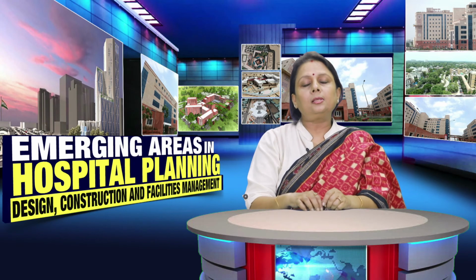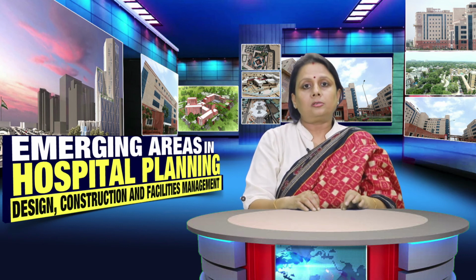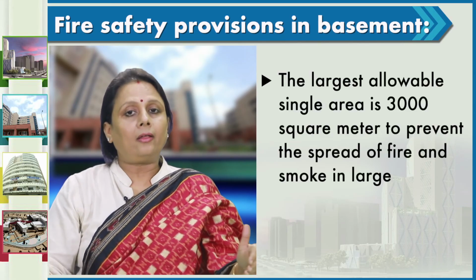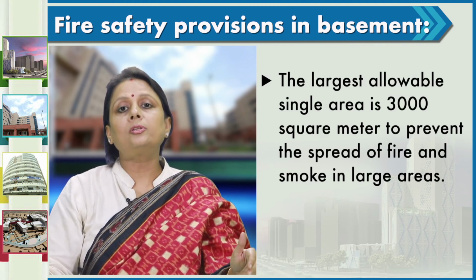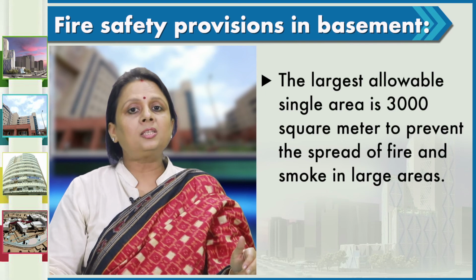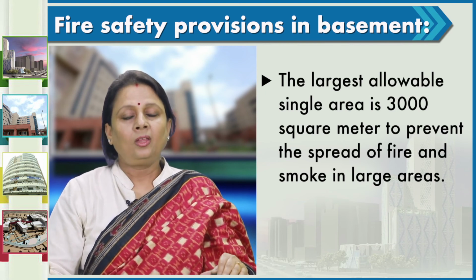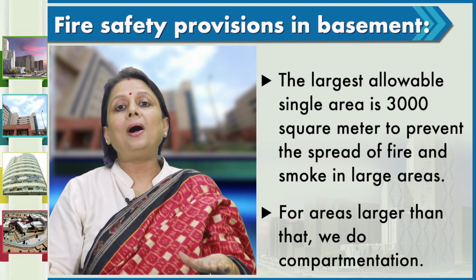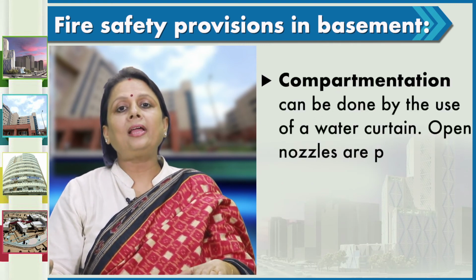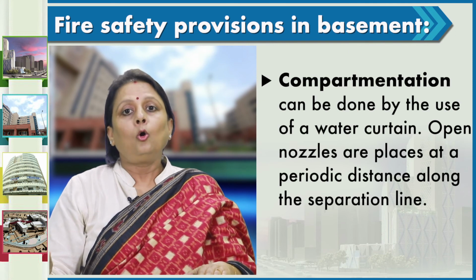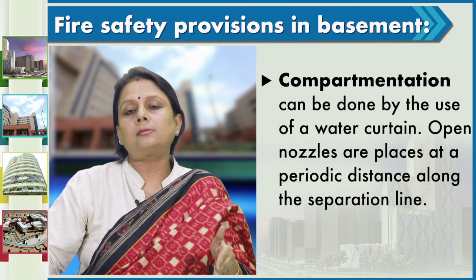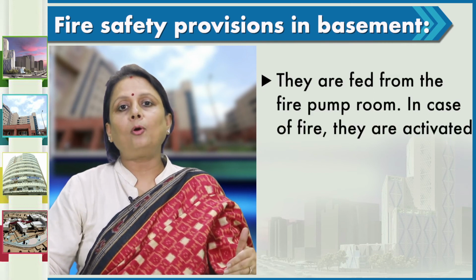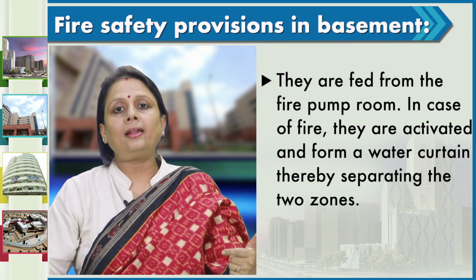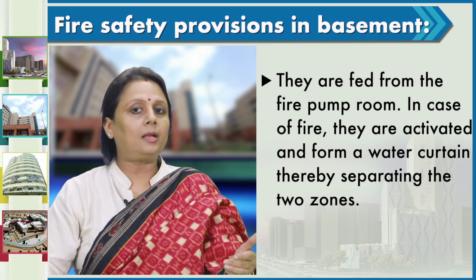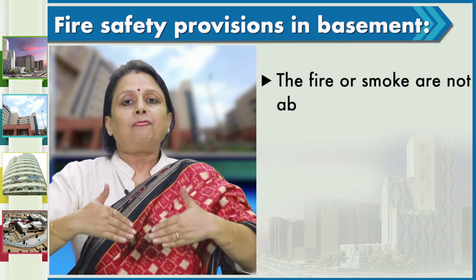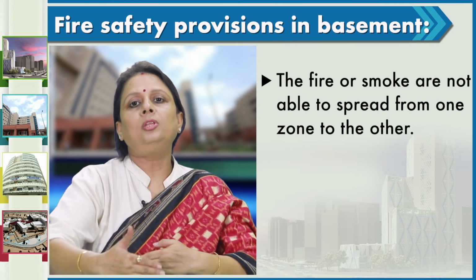Fire safety provisions in the basement are very important. The largest allowable single area anywhere, especially in the basement, is 3000 square meters, so as to prevent the spread of fire and smoke in large areas. For areas larger than that, we do compartmentation. Compartmentation can be done by the use of a water curtain. Open nozzles are placed at a periodic distance along the separation line. They are fed from the fire pump room. In case of fire, they are activated and form a water curtain, thereby separating the 2 zones. The fire or smoke are not able to spread from one zone to the other.